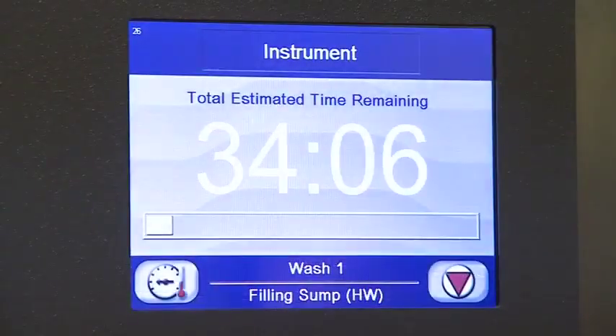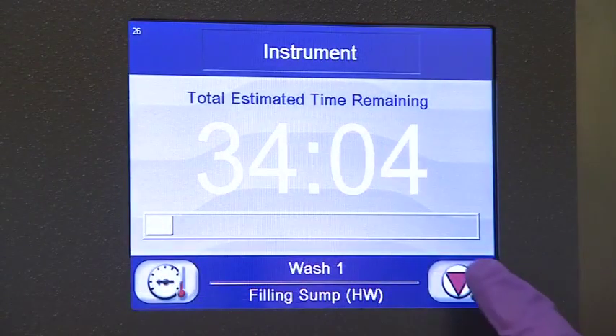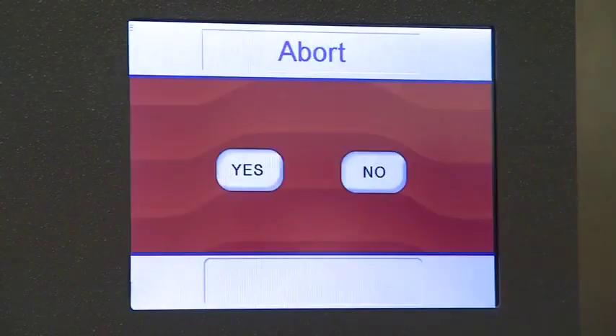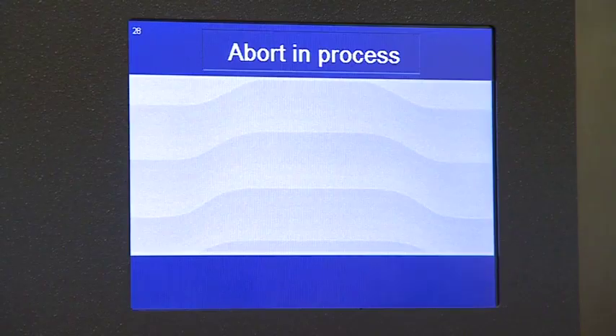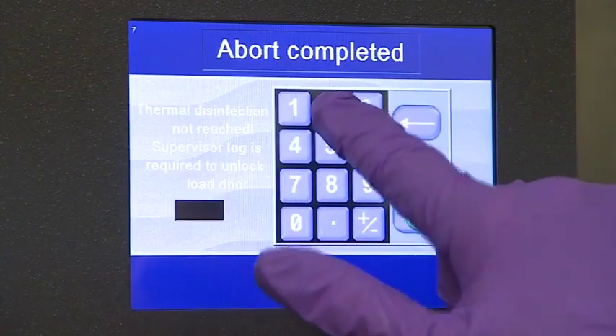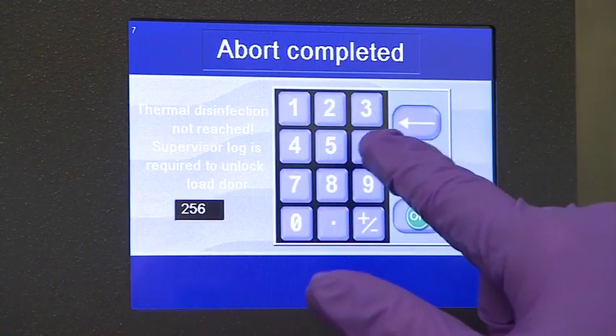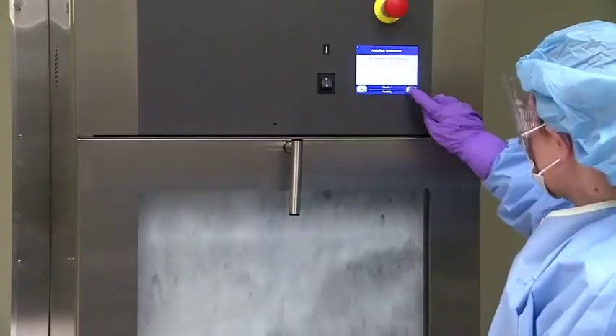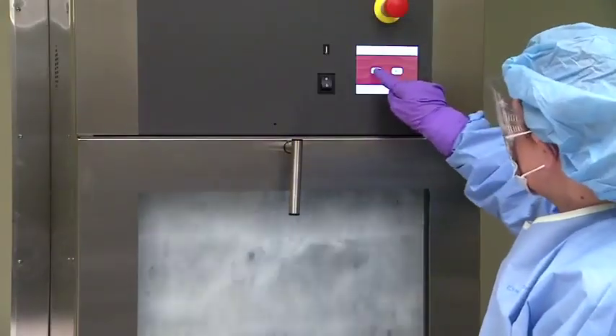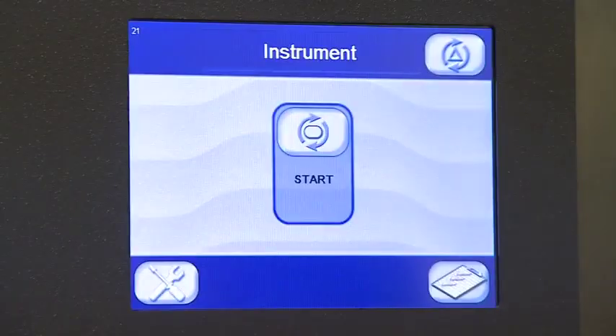Sometimes, there are occasions to interrupt or stop a cycle before it's complete. If a cycle needs to be aborted for any reason, press the Abort button on the touchscreen, then hit Yes to confirm the abort sequence. A supervisor password might be required to abort a cycle. Once the abort process begins, the unit drains, briefly vents, and the display returns to the cycle screen.